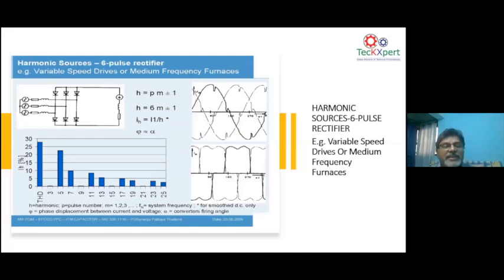Now, if you take a 6 pulse variable frequency drive, as I told you, here you have 6 diodes, unlike in an SMPS, where there are 4. So when you have 6 diodes, you can see that 6 plus minus 1 becomes 5. That means a variable frequency drive, which is a 3-phase UPS or 3-phase drive, will start producing harmonics from the 5th onwards. So you can see here the 5th harmonic, 7th harmonic, and like that it progresses.